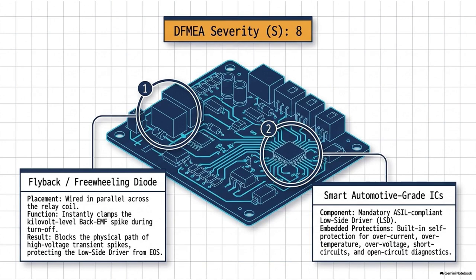But what happens if it loses the race? If the BMS gives the circuit roughly 300 milliseconds to cross that 95% threshold, and I'm sitting at, say, 50% voltage when the timer expires, what does it do? The guillotine protocol. It instantly triggers the P0AE1 or P0A2B diagnostic trouble code and aborts the sequence. The software rigidly commands the pre-charge relay to open. It's a violent, immediate hardware intervention.